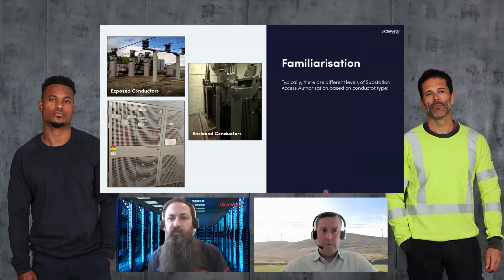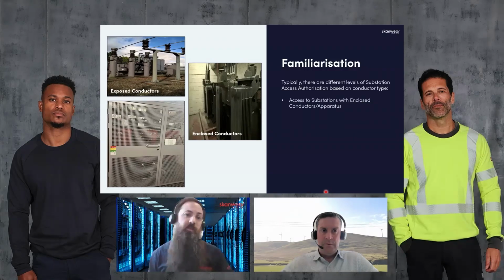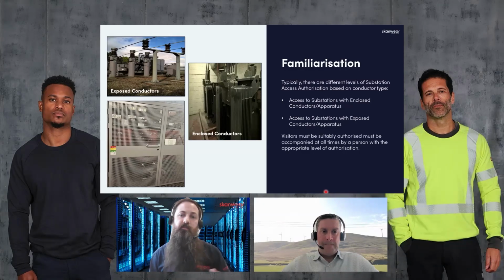Likewise, we've got different types of compounds: substations with exposed conductor, like we can see there; enclosed conductor, when you can't physically come into contact with the parts; and things like cast resin transformers, which have exposed conductor but safety by limits - a cage or enclosure you can't access, linked in with the protection system, hopefully interlocked.